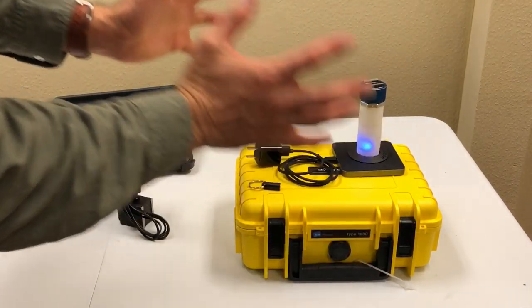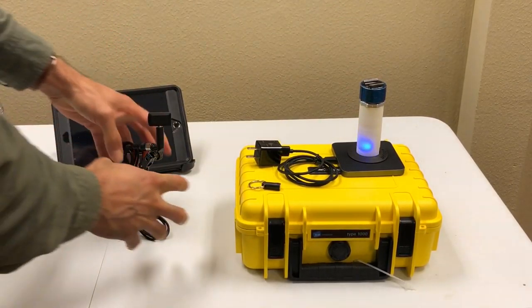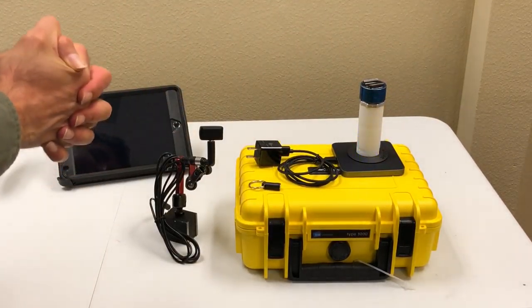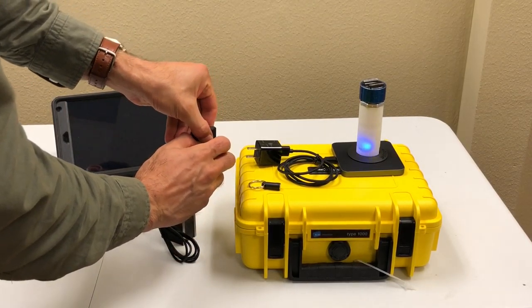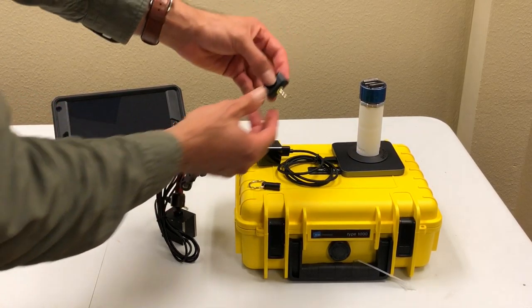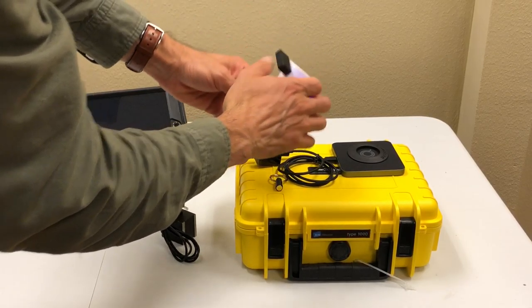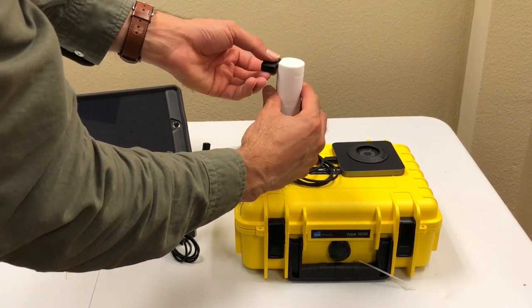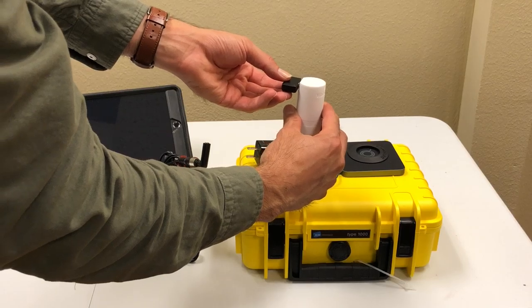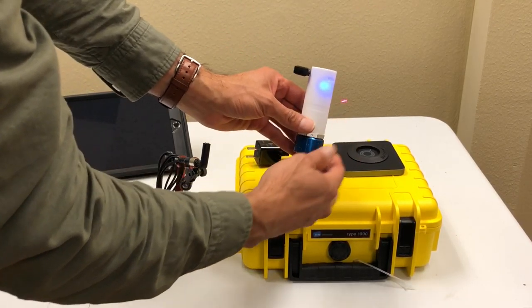As I said, this is VibeSense for vibration. If you need to use this whole system for rotor balancing, you need a few other pieces called together the VibeSense Balancer. The core part of the balancing add-on is a laser sensor that directly connects to the VibeSense. It's powered through the VibeSense and transmits a laser signal, receives it back, and reads the RPM as well as the phase angle of the sensor.